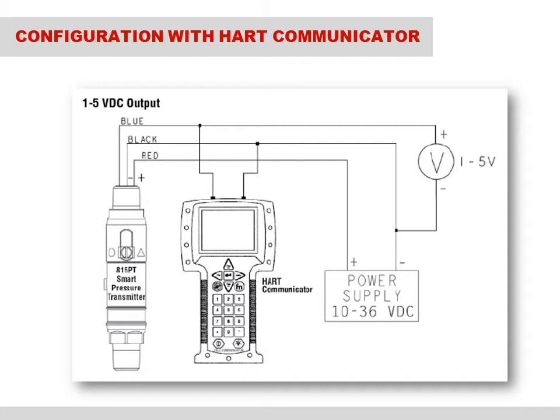Simply connect the HHC's lead set to the blue and black flying leads on the 815. Note that a load resistor R sub L is not required for this output configuration. Also note that the red wire is still required because the red and black wires provide power to the 815 PT. As stated previously, the pictorial diagrams on these slides depict what one would see in a laboratory benchtop setup rather than a plant environment.